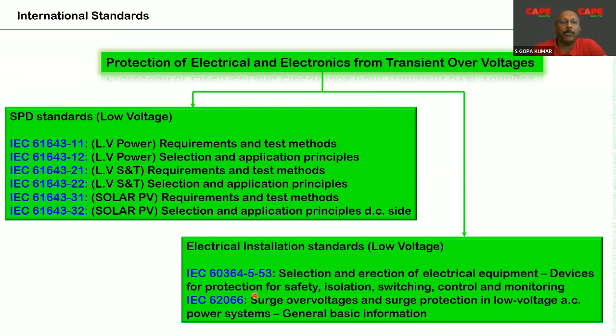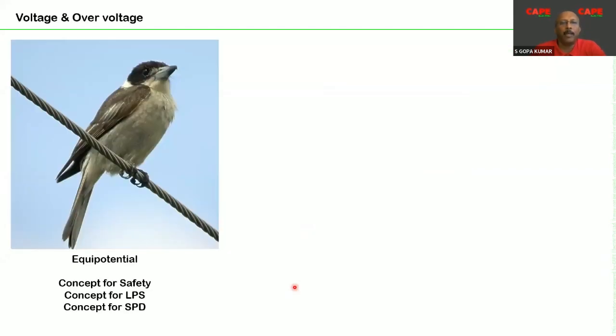When you install an SPD in a line, in an installation, you should also look into the standard IEC 60364, which talks about the selection and erection of electrical equipment, devices for protection for safety, isolation, switching, control and monitoring. Especially SPDs are also explained here. So when you select or install an SPD in a low voltage line, we also should take care of the requirements of these particular standards. In these two seminars, part 1 and part 2, we will discuss the various requirements from these standards. Of course, two seminars are not enough to create complete awareness, but we will try to make it as good as possible.